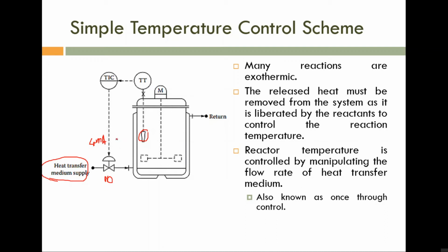And if you are giving 20 milliampere, then the valve is closed. So please note, if we want to close, then we have to give 20 milliampere. If we want to open, then we have to give 4 milliampere. Is it clear? Now TIC.